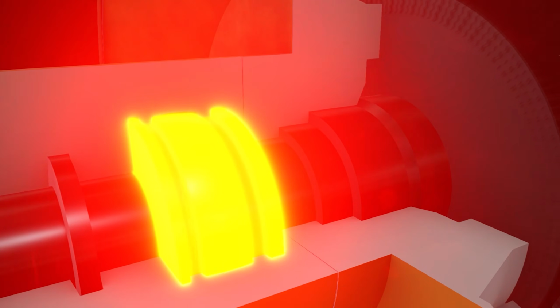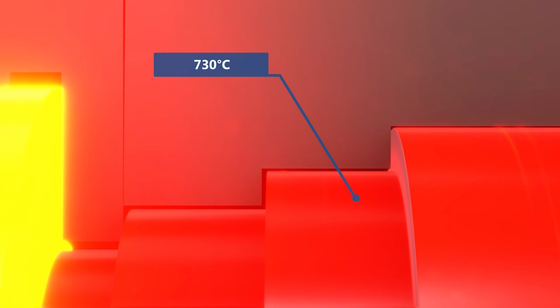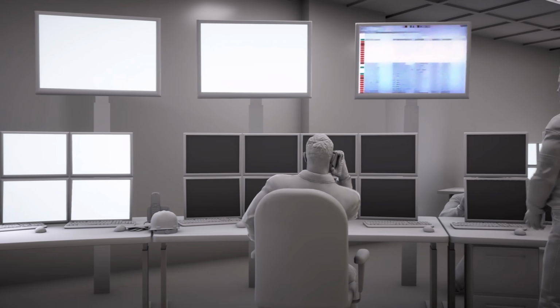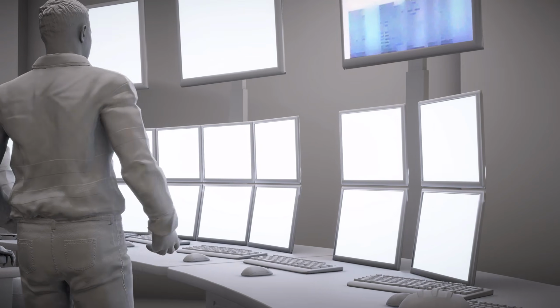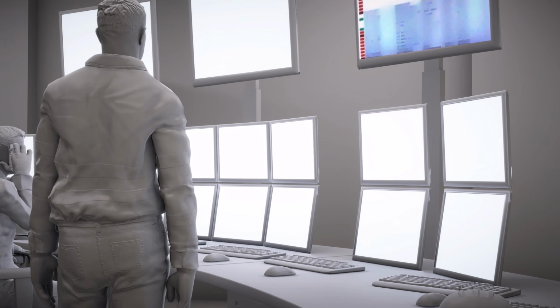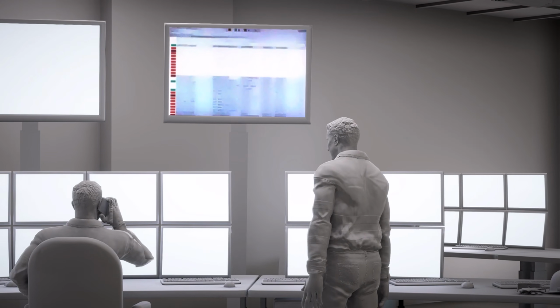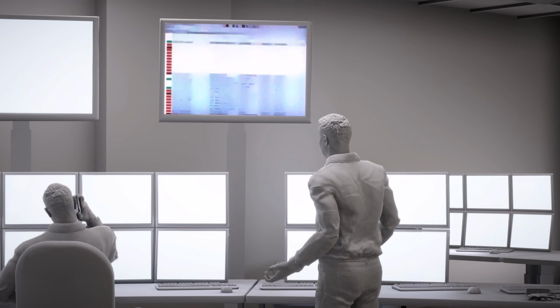Because the white metal layer of the bearings has completely melted away, the shaft begins to lose its center. Ongoing grinding generates immense heat. At this stage, the shaft has reached at least 730 degrees Celsius. 20 minutes later, the operators managed to restore their displays using another power source. But it's clear to the operators that the incoming data is inconsistent and can't be relied upon to make a safe and informed decision. Their major concern is avoiding an overspeed event.